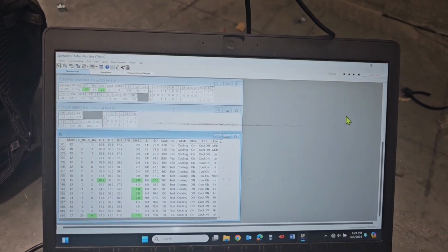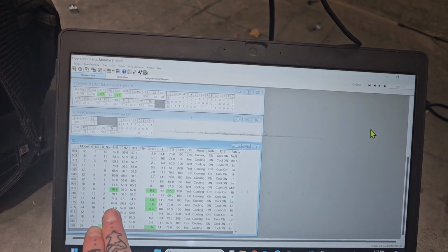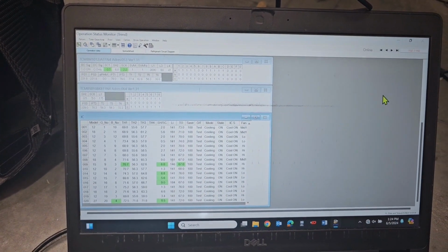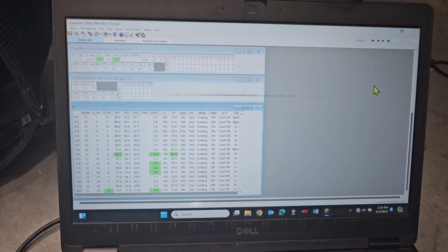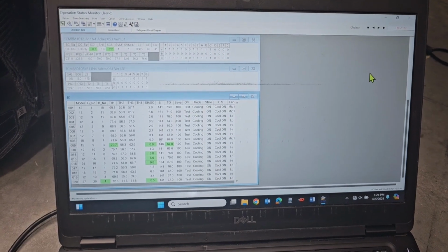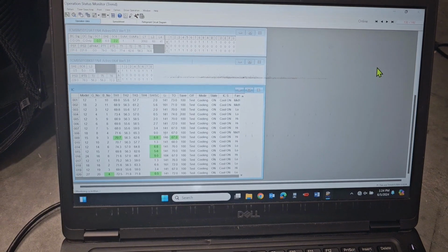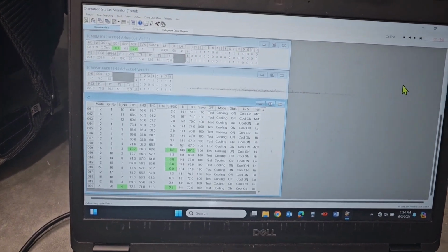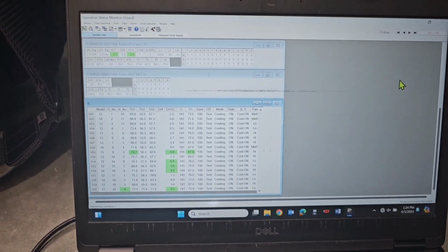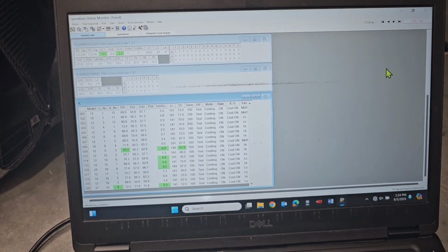So again, after more testing, I went around and opened up these 3 ports again. I left this 4th port closed because that one was the biggest outlier of them all, seeing as how it had such low superheat. So I put it into test mode again, let it run, and everything was pretty much more or less running fine.